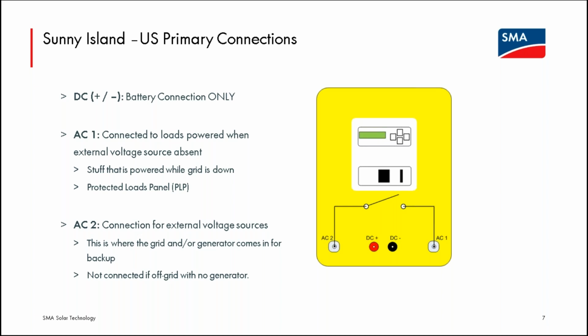But there are DC positive and DC negative shown here. Only the battery connects to that. Again, things can couple on the DC side, but that is the battery connection. The AC1 terminals are the AC terminals, line, neutral, and ground, to provide that 120 volt, 60 hertz waveform if the Sunny Island is taking power from the battery and creating that waveform.